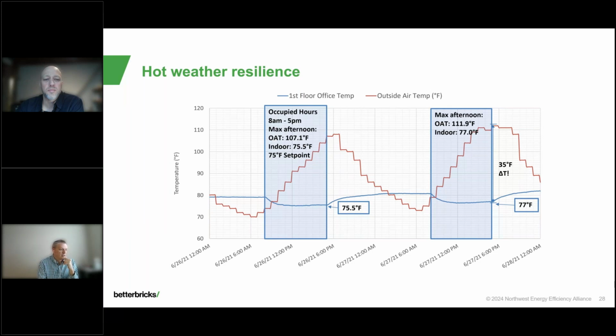It's been about 3 years now—time flies. We had a heat dome, with a few days in a row at or above 110 degrees outside. We tracked and monitored the building, with an inside set point of 75 degrees, and on those two heat dome days we kept the inside temperature at a 35-degree delta T even with it so hot outside. The energy use wasn't massive compared to other buildings that couldn't keep up with the cooling needs during those heat domes.